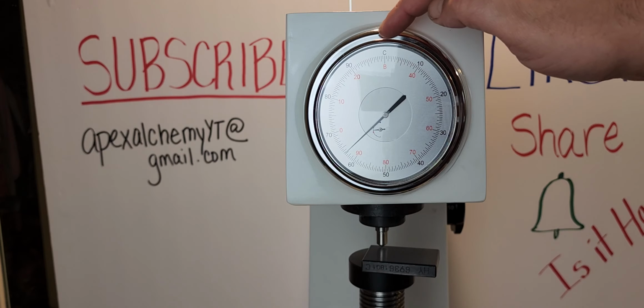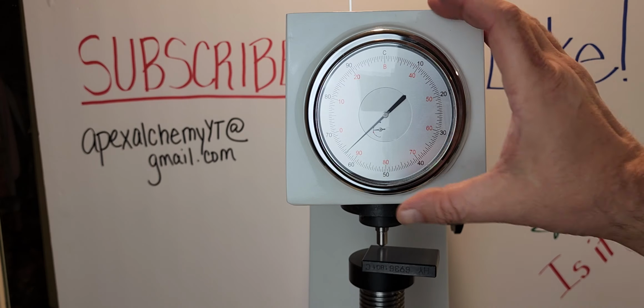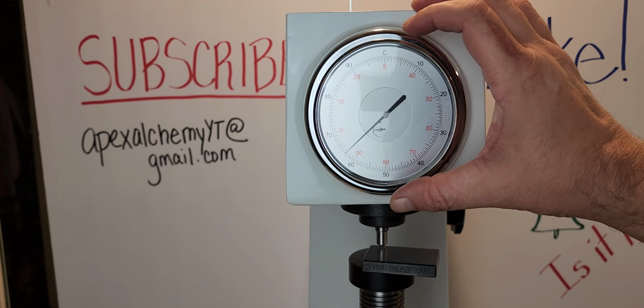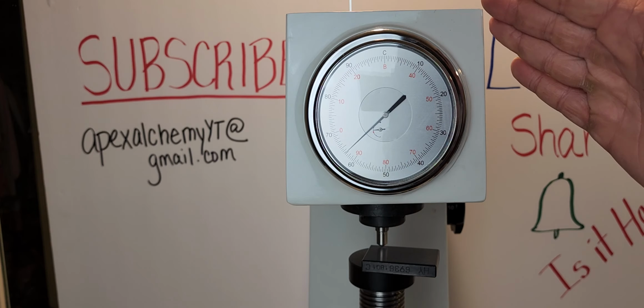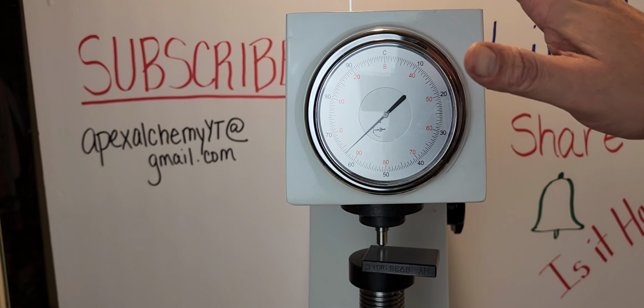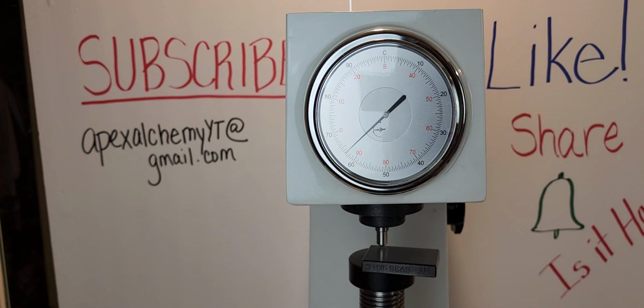So the C up here is 0. Further away we get from that, you can make those little minor adjustments like this for a little while. But once you get a few points off one way or the other, you need to go back and calibrate the machine. It don't take that long. But this video is longer than it should be. It should have been like a 3-minute video, just testing HRC. For those of you who are still here, you got to see a calibration in the works.